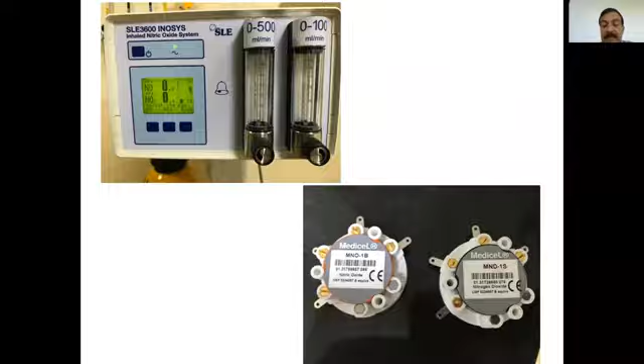These are calibrating gases. These are the smaller canisters, about 1.6 liters, and this is the first one on the left hand side, for nitric oxide calibration. Before that, first do not connect the nitric oxide; connect this. There is a vent at the back side where we connect the oxygen or the air at 1 liter per minute. Once we zero it, then we connect the nitric oxide canister first, and then it is calibrated up to 25 parts per million, which takes almost 15 to 20 minutes.